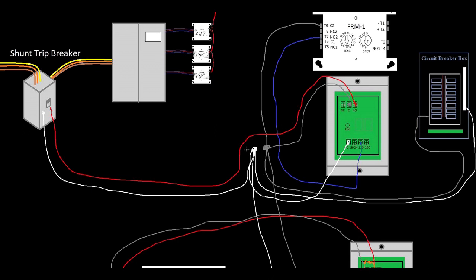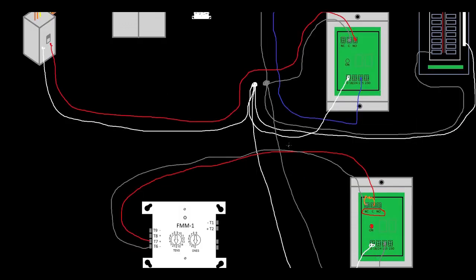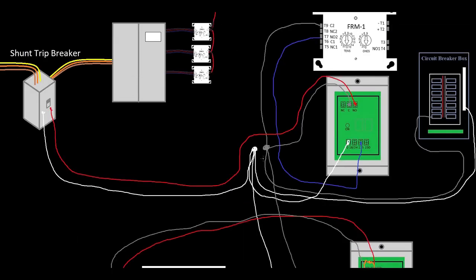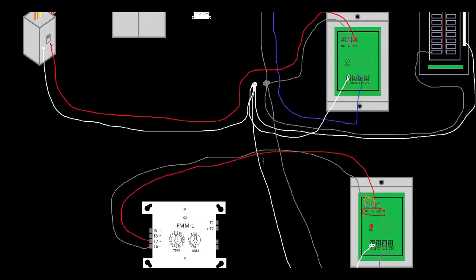You're not going to have four neutrals coming off. You'd probably realistically come into one of your MR101s, come out of the other or come out of that into the other MR101 and then out of that directly to your shunt trip breaker, so you don't even necessarily need a wire nut if you do that correctly. The hot you're still going to need a splice, but you can still do it more creatively. You could come into one common, out of that common into the other common, out of that into the trigger down low if you needed to. It doesn't have to be as crazy as it looks here. The reason I made it this crazy is to be able to draw one step at a time and make it all make sense.